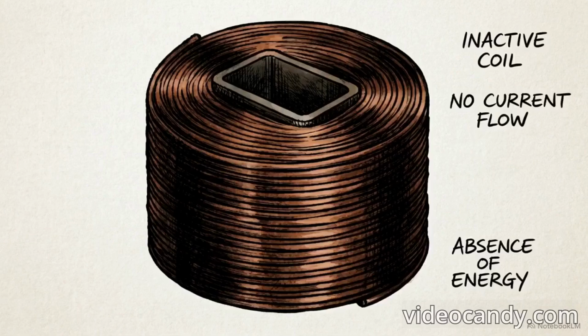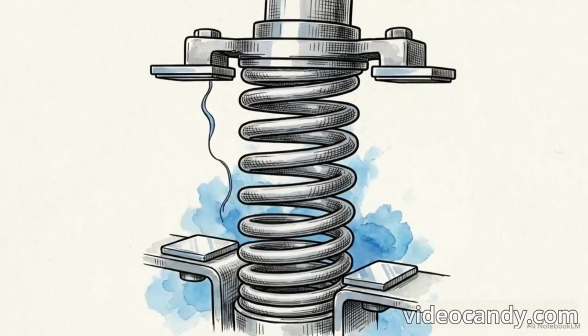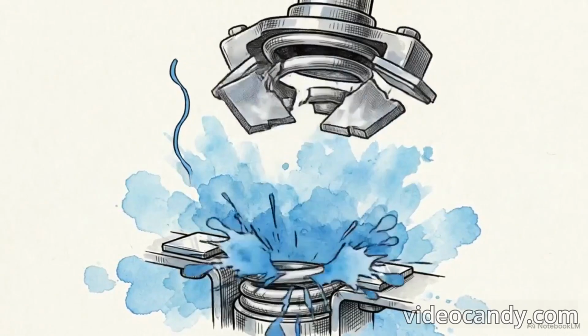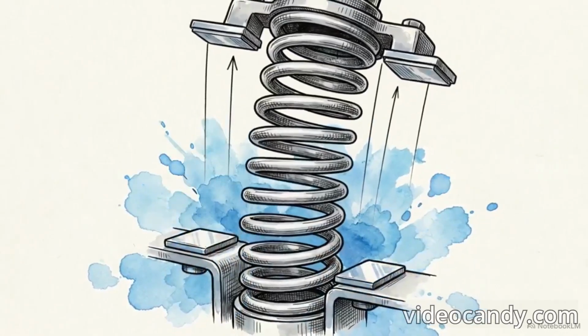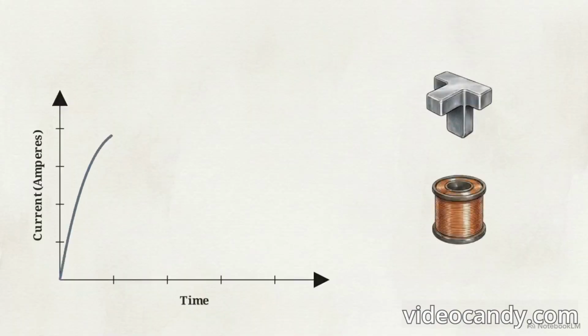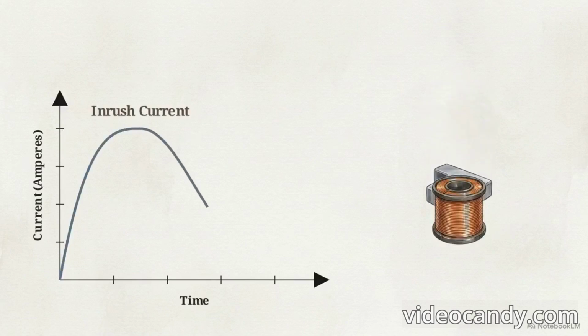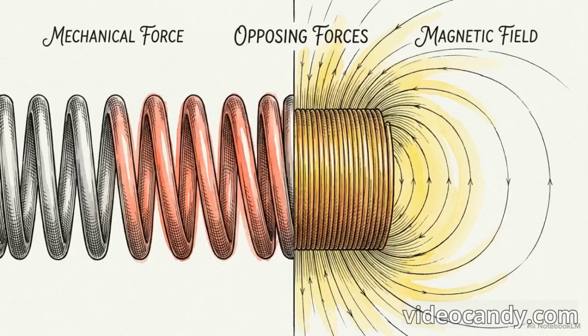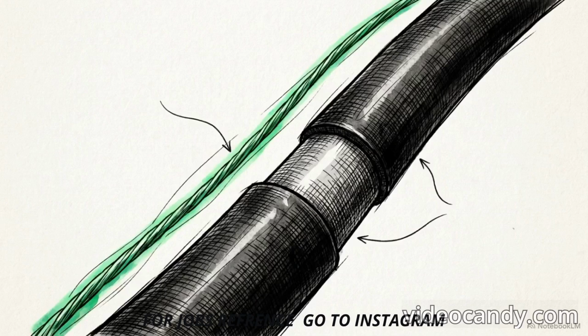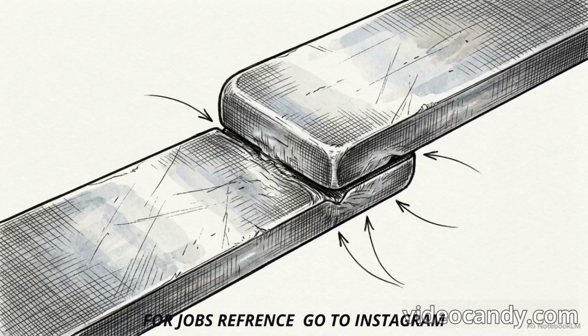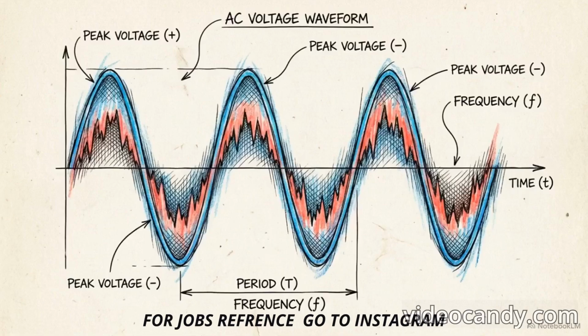The moving contact pads slam into the stationary pads, instantly completing the high-power circuit and allowing current to flow into the motor. The moment that control voltage is removed, the magnetic field collapses. The compressed backspring instantly decompresses, forcing an immediate, rapid physical separation of the heavy silver contacts to halt the power flow. During this process, the coil draws a very high initial inrush current. As the metal core is fully pulled down inside the coil, that spike rapidly drops to a lower holding current. This precise calibration between the mechanical tension of the spring and the magnetic pull of the coil is what allows a tiny 24-volt DC signal to safely command hundreds of amps of alternating current.